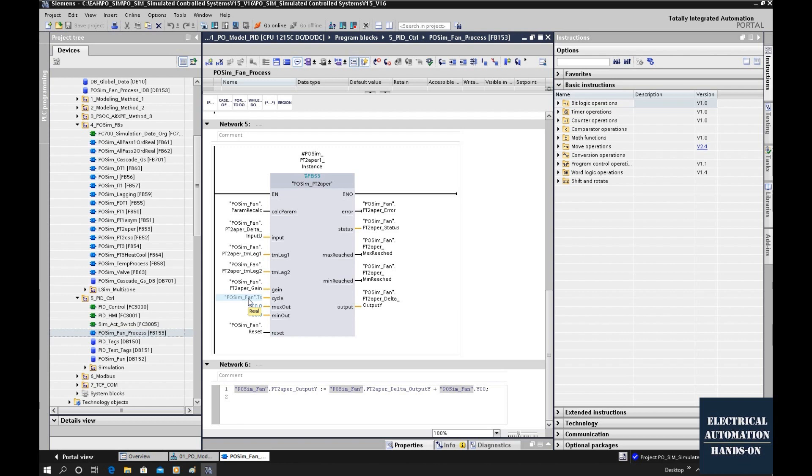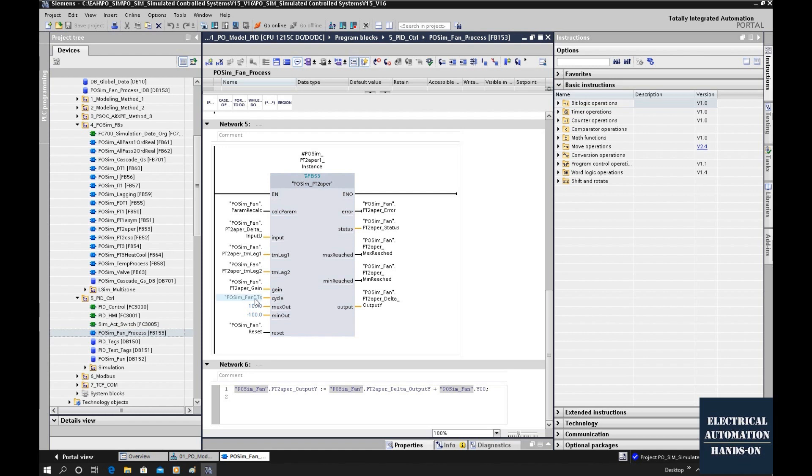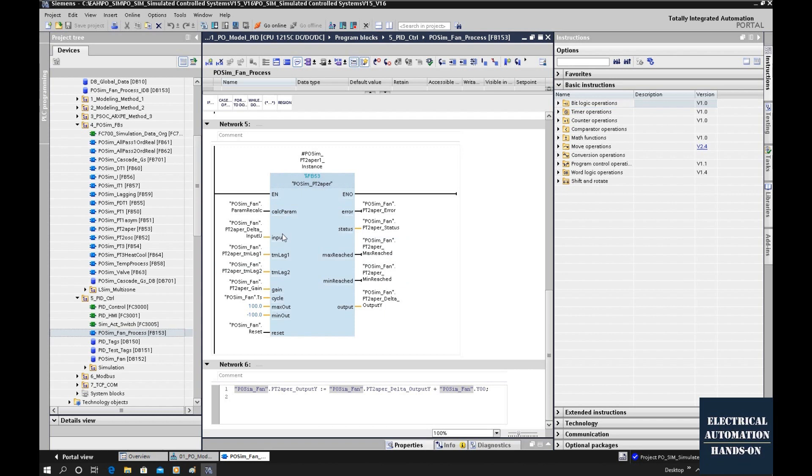In my project, this cycle time is 2 seconds. If you recall, when I recorded the data, I used 2 seconds as a record sample time to record the data. Then I used those recorded data to identify the process model. That's why when I implement this function block, because this transfer function comes from the MATLAB system identification, I must use the same sample time, that is 2 seconds.